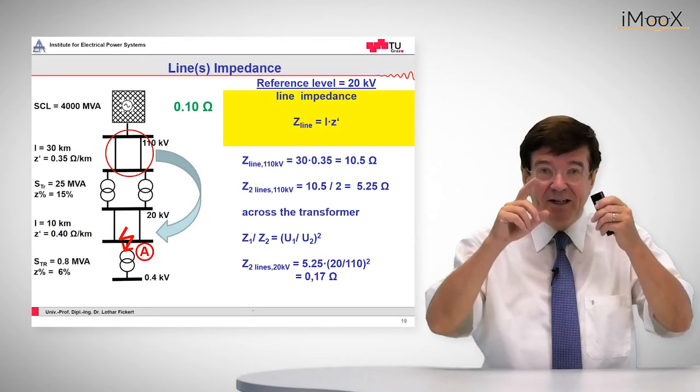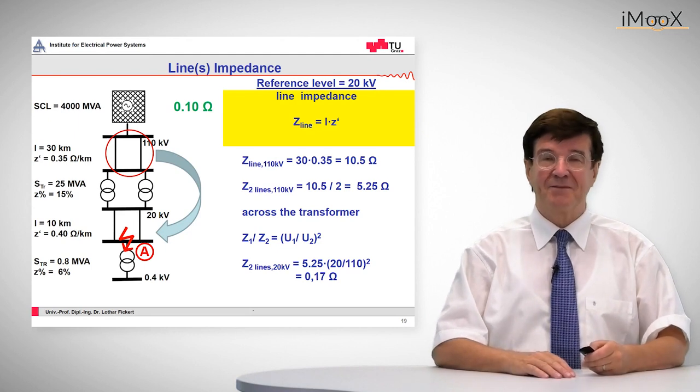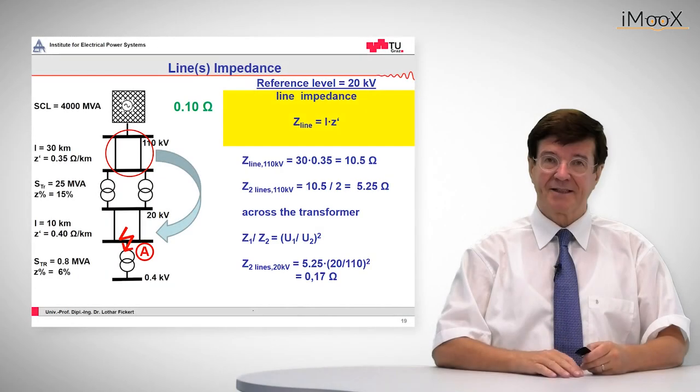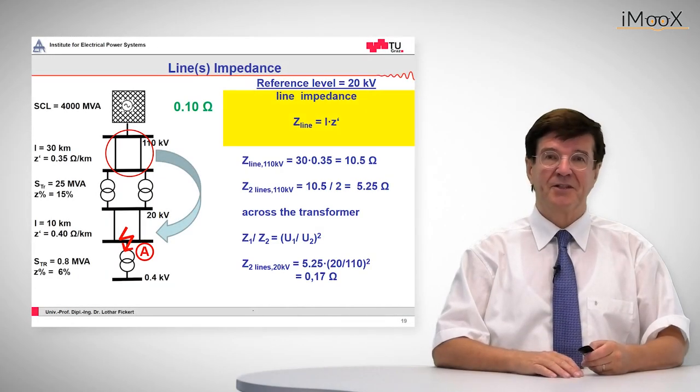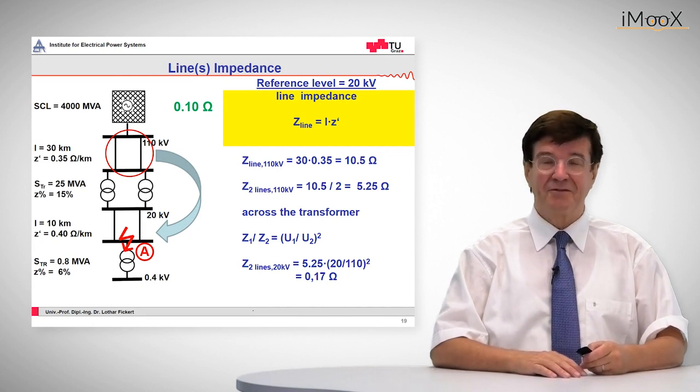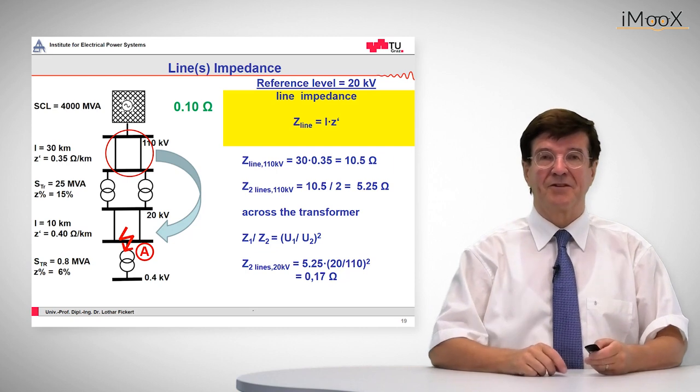So this is the real impedance for these 110 kV lines, but they must be transferred to the 20 kV side of the transformer, and that is done by the square of the voltage ratio. So on the 20 kV side, these 110 kV voltage lines have an apparent impedance of 0.17 ohms.